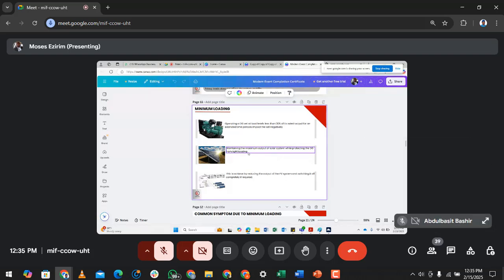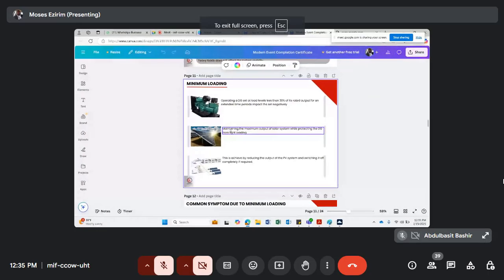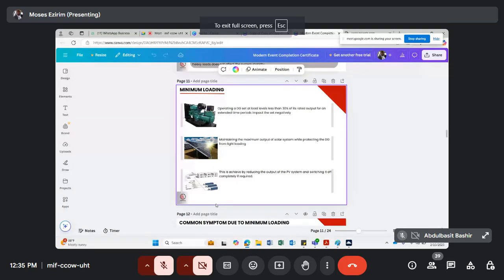All right. So this simply means that even during peak sun hour, let me assume that for this installation, with this same 1000 kVA generator that I mentioned, the base load is 240 kilowatts. Now, if I install 1,500 kilowatt peak solar capacity, at peak sun hour, if the client load is 700, I'm sure you know that an installation of 1,500 kilowatt peak should be able to carry the whole 700.